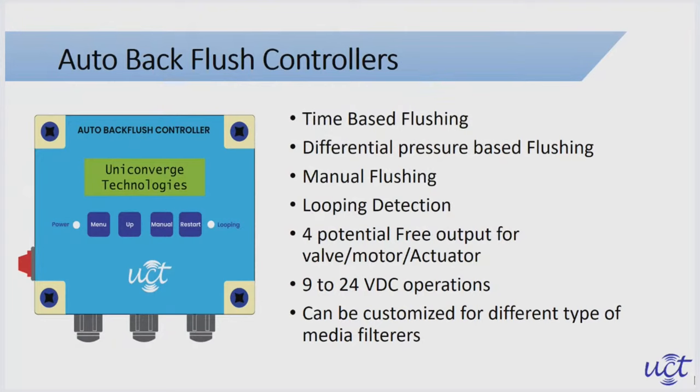But now this can be done on a time basis. Also, it can be done based on sensors. We have a differential pressure sensor which senses that there is choking in the filter, and then it automatically cleans the filter. We can also manually flush the filter. There is also looping detection: if there is any problem with the sensor, or the filter is totally clogged up, it gives us an alarm that the filter is clogged, jammed and not working properly. So a user can go there and check.